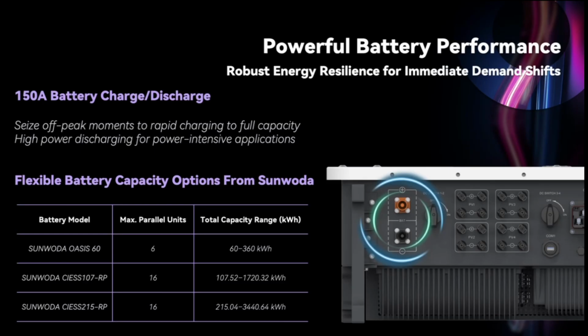For example, if we connect with the Sunwoda OASIS 60, this battery supports up to 6 units in parallel, and in this case, the total capacity range could be from 60 kilowatt hours to 360 kilowatt hours. And if we connect with the Samuda CIESS series, the 107 RP, this battery supports up to 16 units in parallel, and the total capacity range is from 107 kilowatt hours to 1.7 megawatt hours.